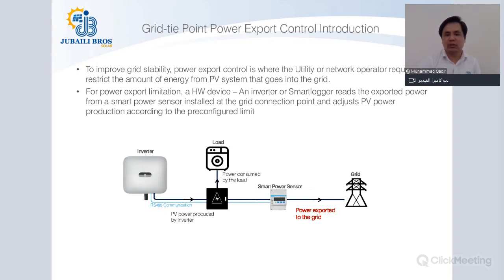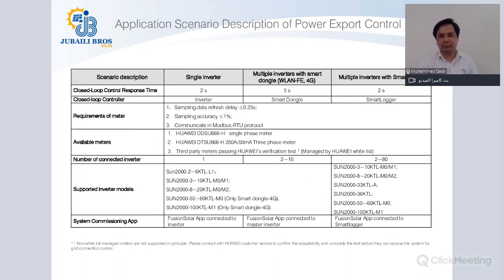Normally the purpose of grid limitation is either that your network doesn't support the big feed-in towards the grid itself, or you are limited by the grid authority to generate a certain amount of power, and you have to control your output if the generation goes above that value. The application scenarios for power control are: a single inverter where you need power control, multiple inverters using a smart dongle, or multiple inverters using a smart logger.